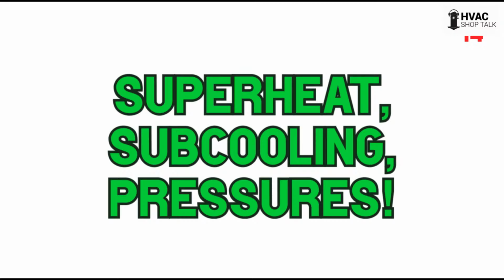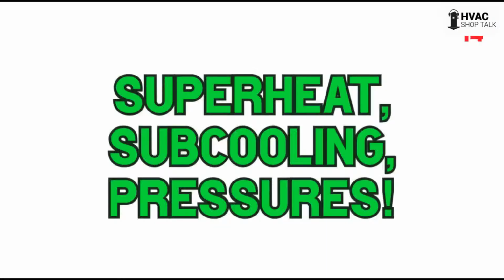It's not as bad with TXV systems because they try to keep a certain superheat. But TXVs have parameters. They have tonnage parameters. If you have a TXV, it has 1.5 to 3 tons. That's where you got there. Once you get outside these parameters, it's not going to be able to do the job any longer. And you have to be able to say, okay, this TXV system can be susceptible to airflow, so I need to watch that. And the refrigerant pressures can go all over the place with airflow, too high, too low. So if you don't measure the airflow, none of this stuff's going to be right.